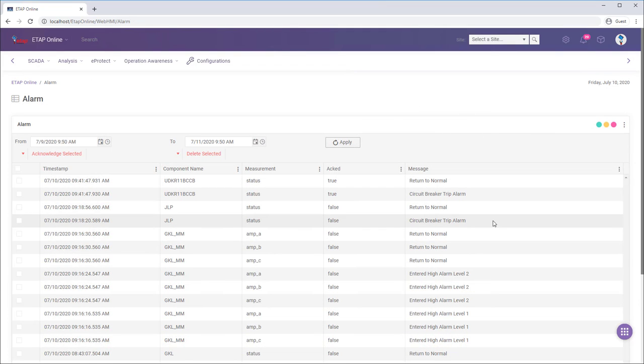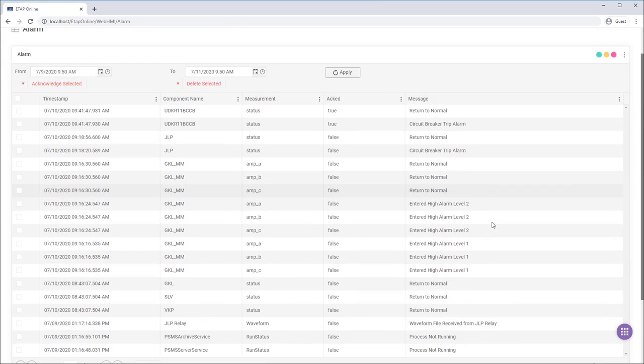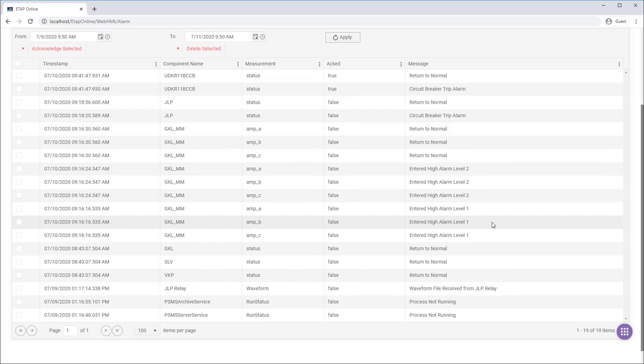In the alarm management system, I can view all the alarms for my area of responsibility and details of each one. Alarms can include communication loss, trip signals, health signals, power measurement thresholds, and disturbance files. Here we can see a waveform file received and as an alerted item. Once reviewed and confirmed, we can acknowledge or delete alarms. As I acknowledge these 2 alarms, you'll notice under the column are now set to true.